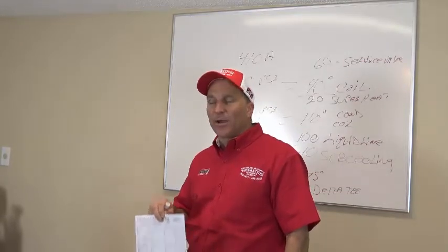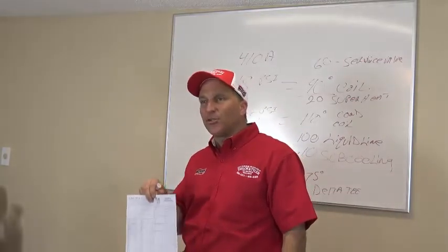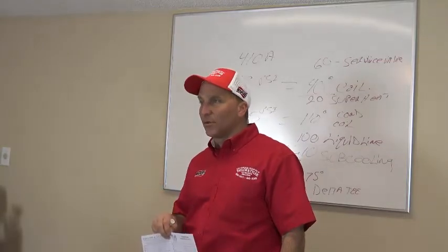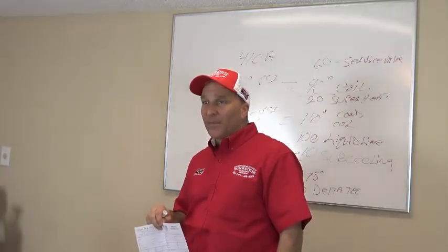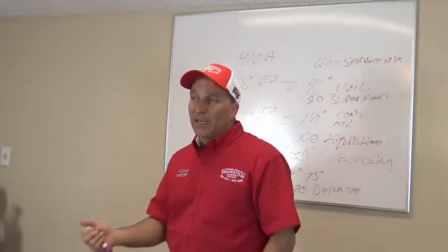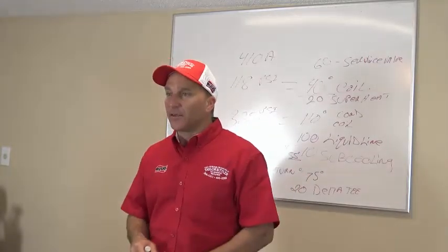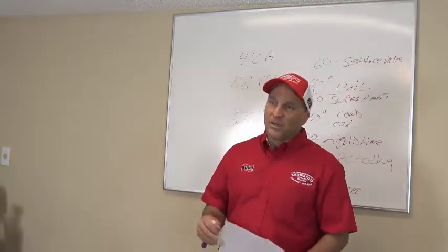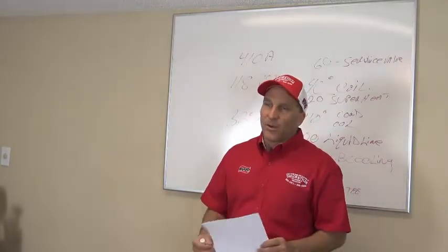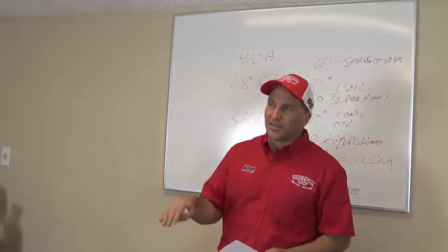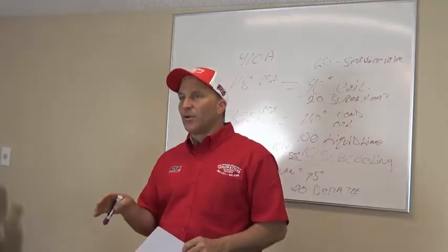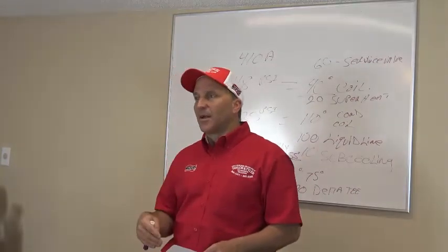You can't get your proper pressures and temperatures unless you clean every condenser you go to. Now, is cleaning the condenser just hitting it with a hose? Is that cleaning the condenser? It'll get a little bit off. The only way you're going to properly clean that condenser, guys, is hitting it with the chemical. Okay? When you hit it with the chemical, then it's going to end up coming off.